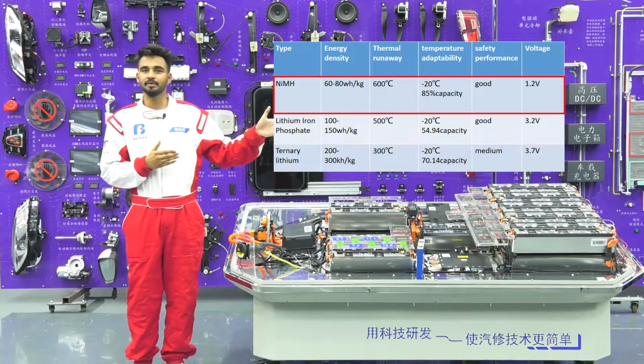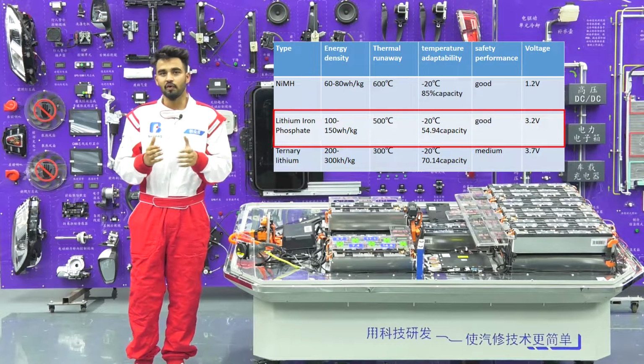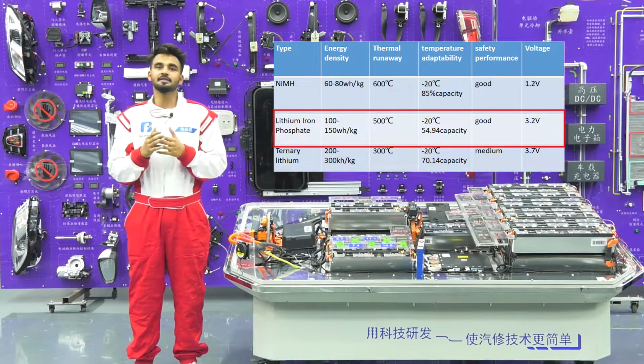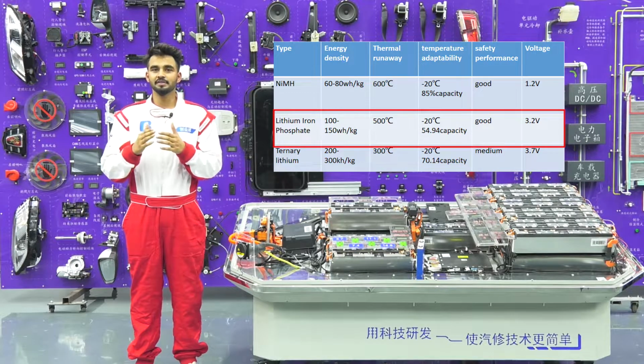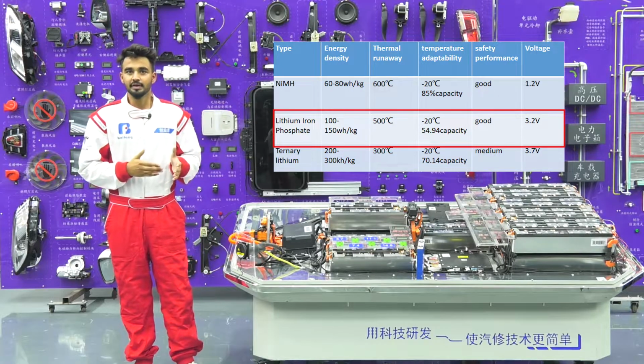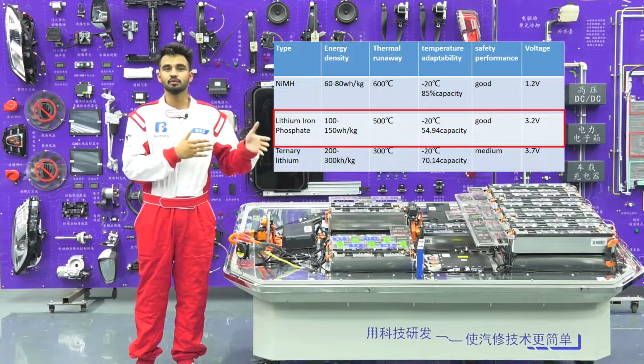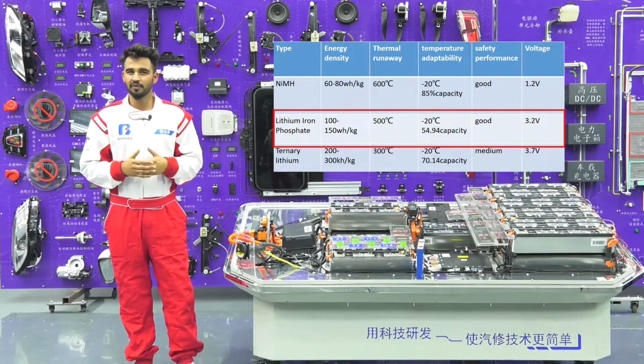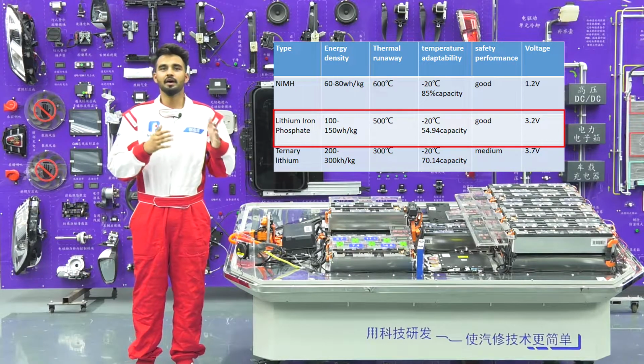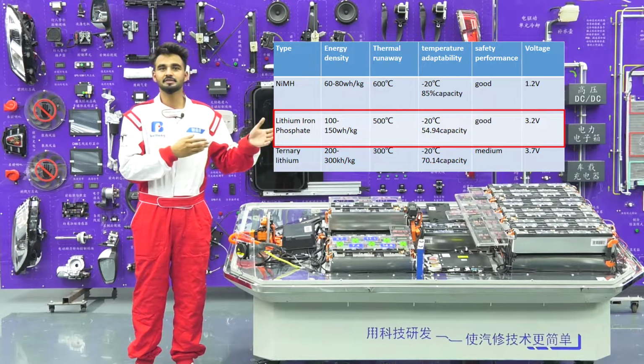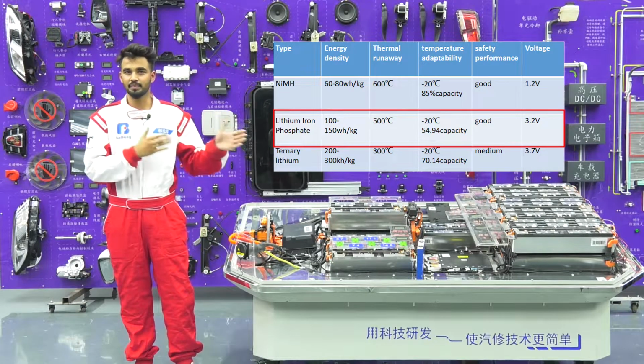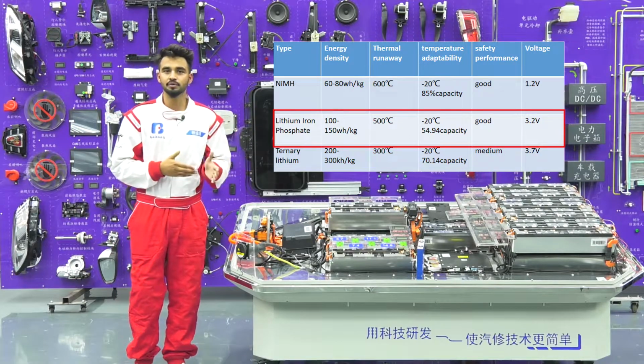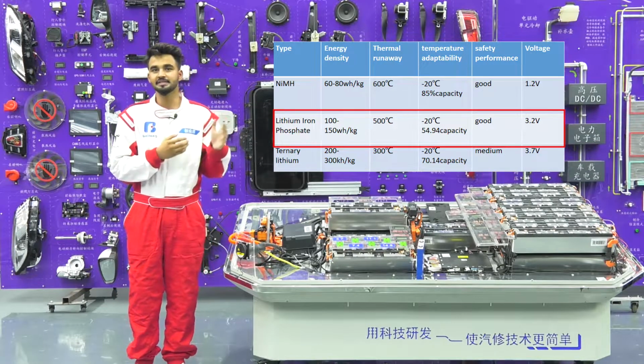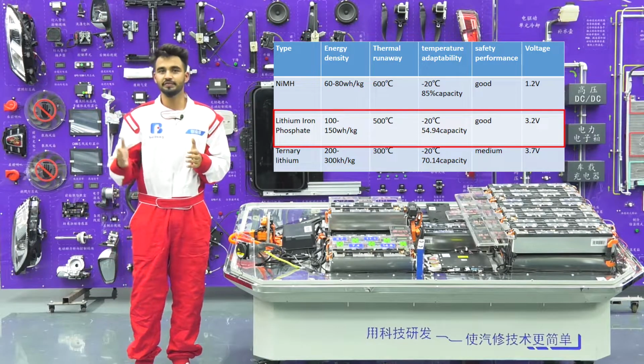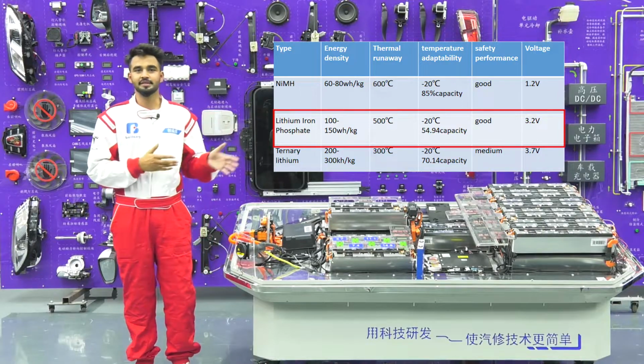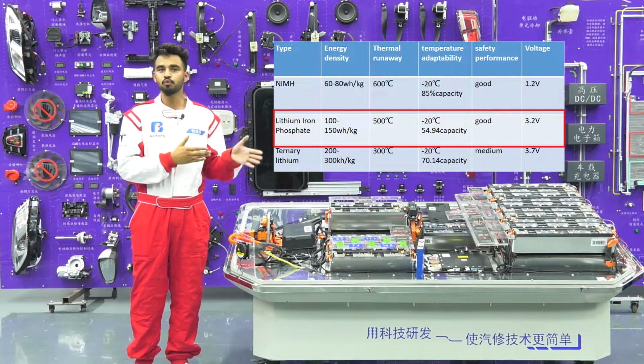The second type is the lithium iron phosphate battery. It's low cost and performs well in high temperature, with good temperature resistance, but in low temperatures like minus 20 degrees, the battery capacity reduces to just 50 to 55%. Its energy density is average, from 100 to 150 watt-hours per kilogram. The battery is safe, and the rated voltage is 3.2 volts.